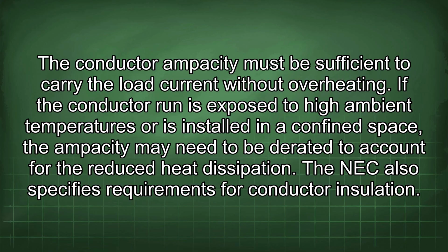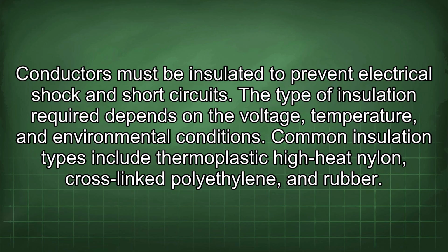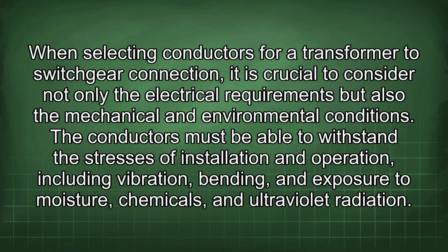The NEC also specifies requirements for conductor insulation. Conductors must be insulated to prevent electrical shock and short circuits. The type of insulation required depends on the voltage, temperature, and environmental conditions. Common insulation types include thermoplastic high heat nylon, cross-linked polyethylene, and rubber. When selecting conductors for a transformer to switchgear connection, it is crucial to consider not only the electrical requirements but also the mechanical and environmental conditions.